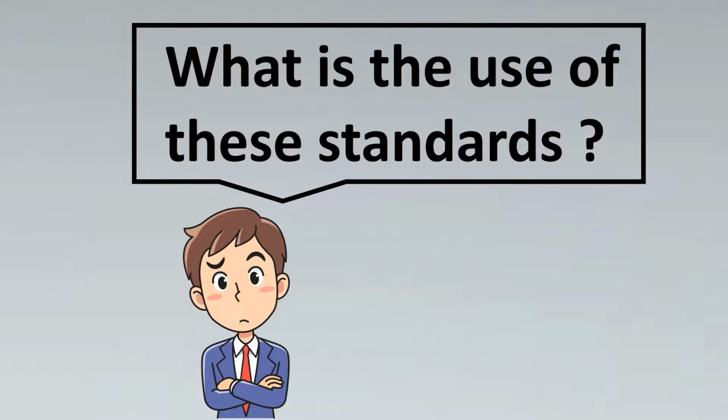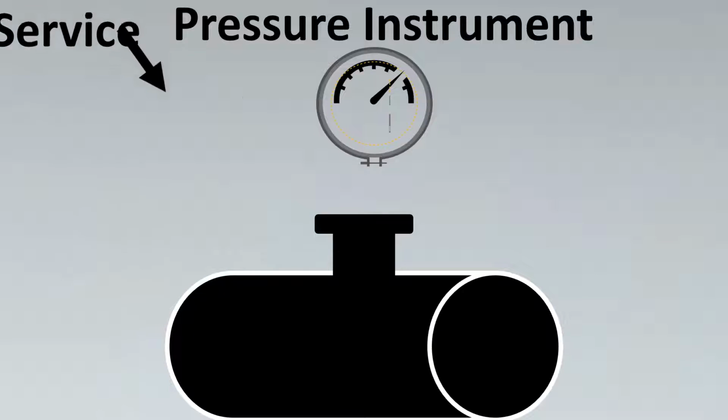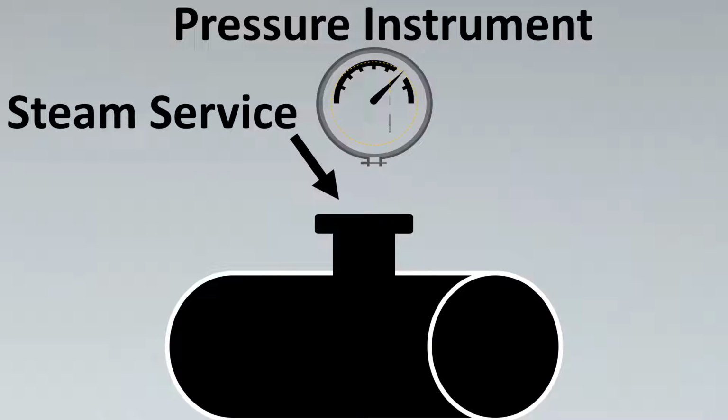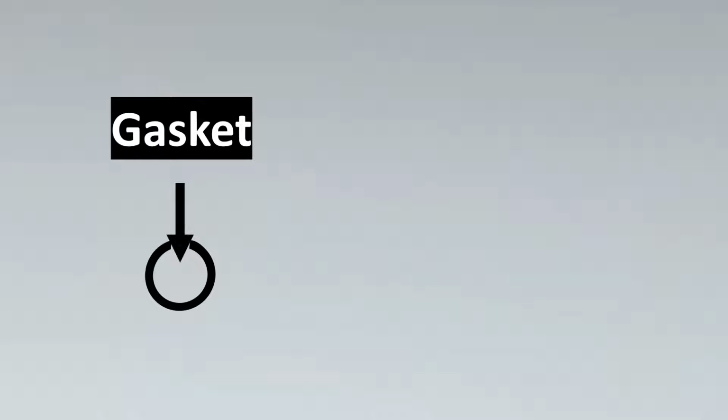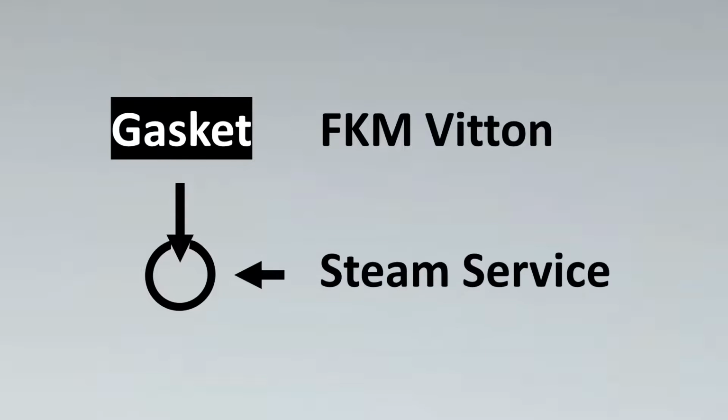You might think, what is the use of these things if this is not mandatory? You might think that we should have some standards which are mandatory. What is the use of recommended practices? I'll share a personal story of mine. I was working on pressure instruments and the service was steam service. I had to work especially on the gaskets. The gasket material was FKM Viton, and this material is not suitable for steam services.